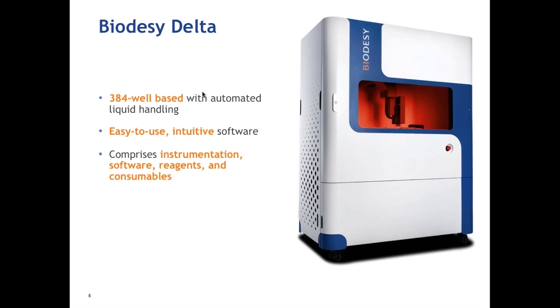We recently, as of July, launched a commercial instrument — the Biodesy Delta. The Delta is about the size of a refrigerator, easy to use, has intuitive software, a custom 384-well microplate, and high throughput. The throughput is roughly an hour per 384 wells, so you can make 384 measurements in that time and look at thousands of interactions of your protein with small molecules, drug compounds, other proteins, and other ligands in a single day.